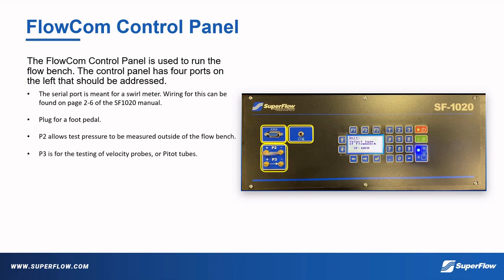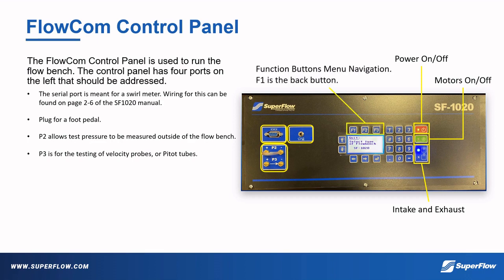P2 allows the operator to test pressures outside of the flow bench, and P3 is used for testing of velocity probes, or pitot tubes. Refer to the SF-1020 manual for more information on these ports. On the right side of the keypad, you'll find the power on-off switch, the motor on-off switch, and the intake and exhaust switch. Pictured, you can see that the intake is selected.